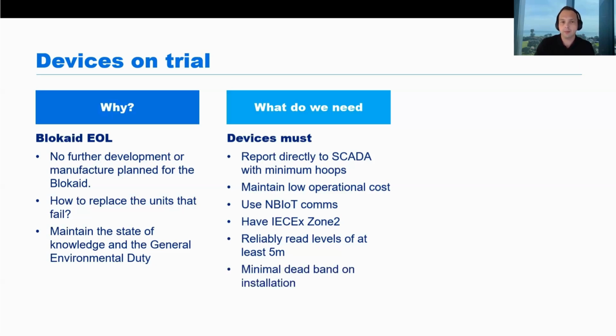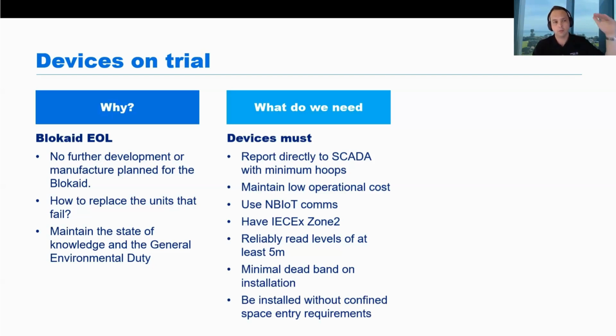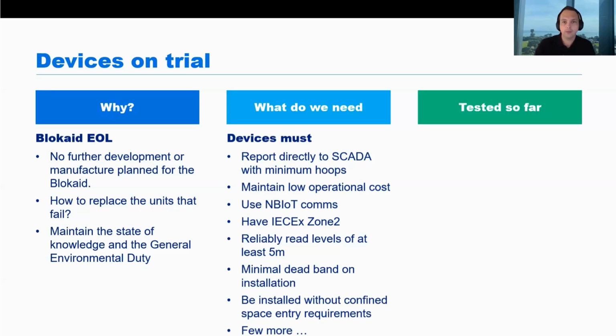And we want to have a minimal deadband on installation, so again referring to the physical size of the device. And we need them to be installed without confined space entry requirements, so they must be installed from the ground level on the manhole opening. There's a few more, but these are the core ones.